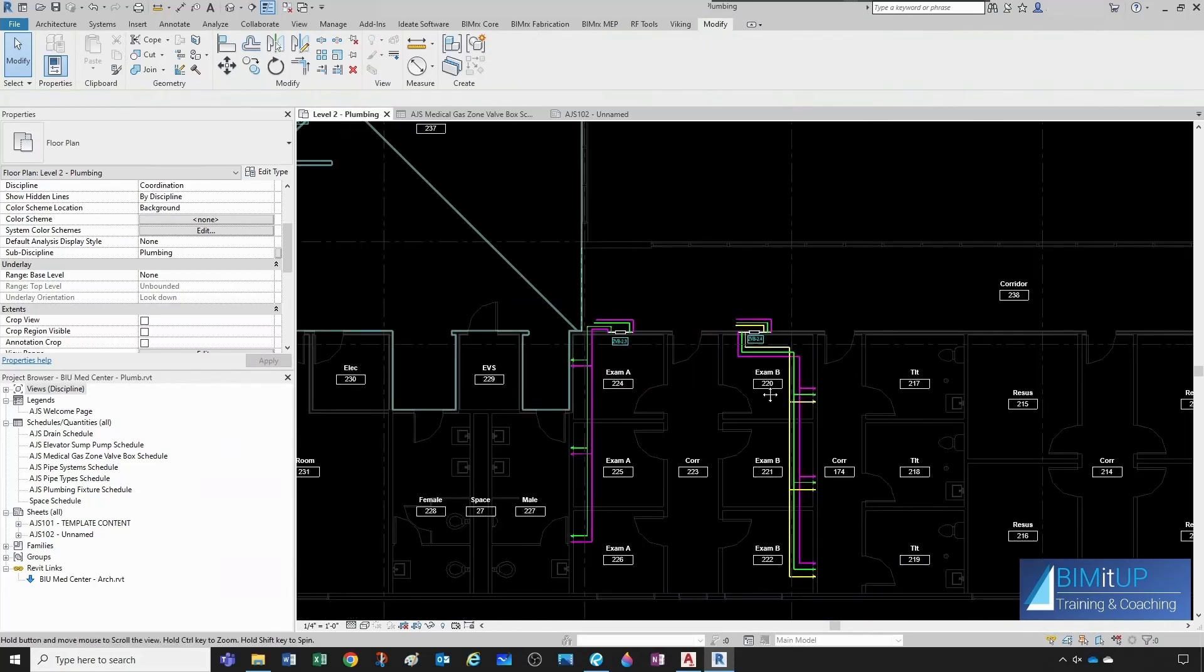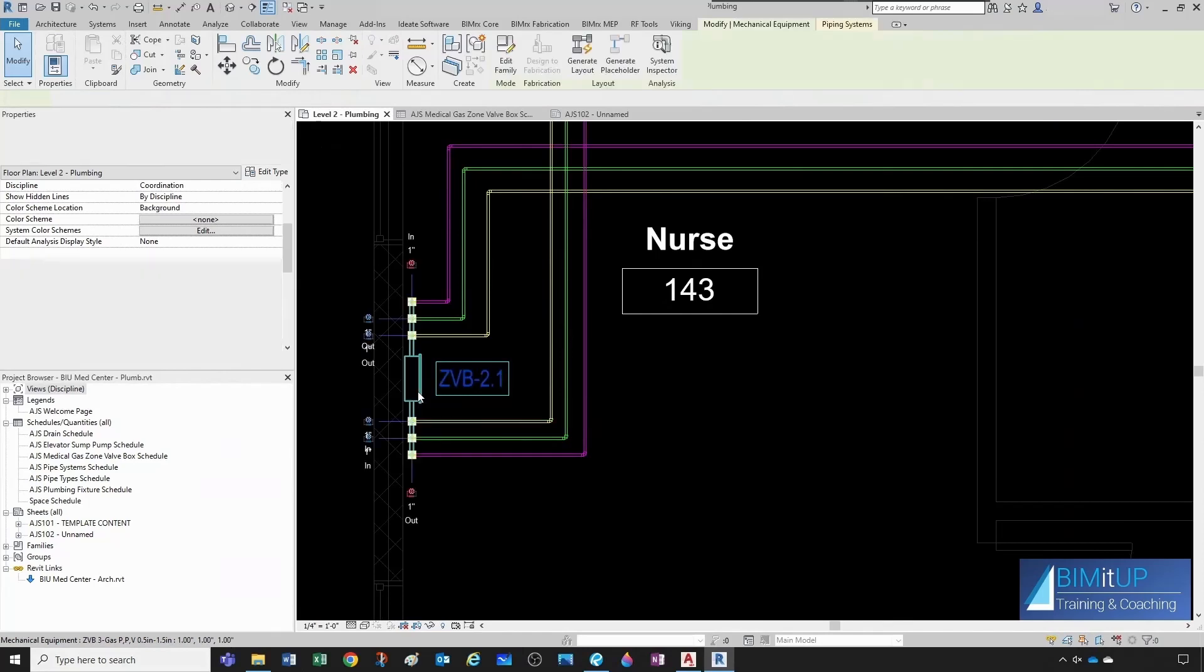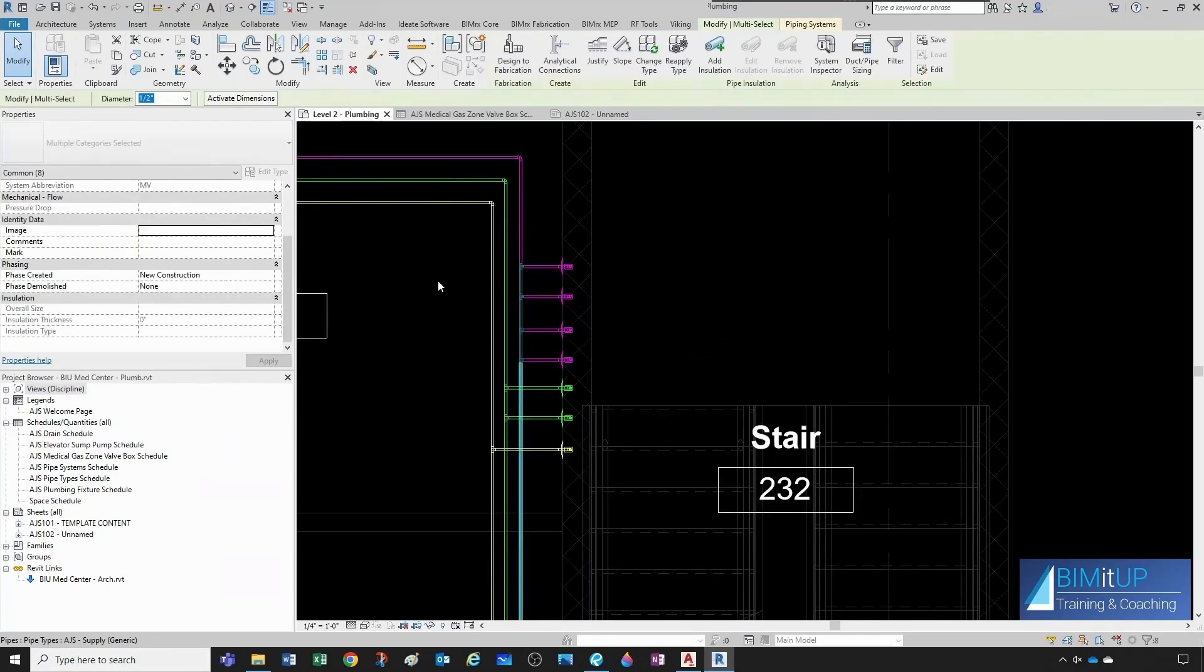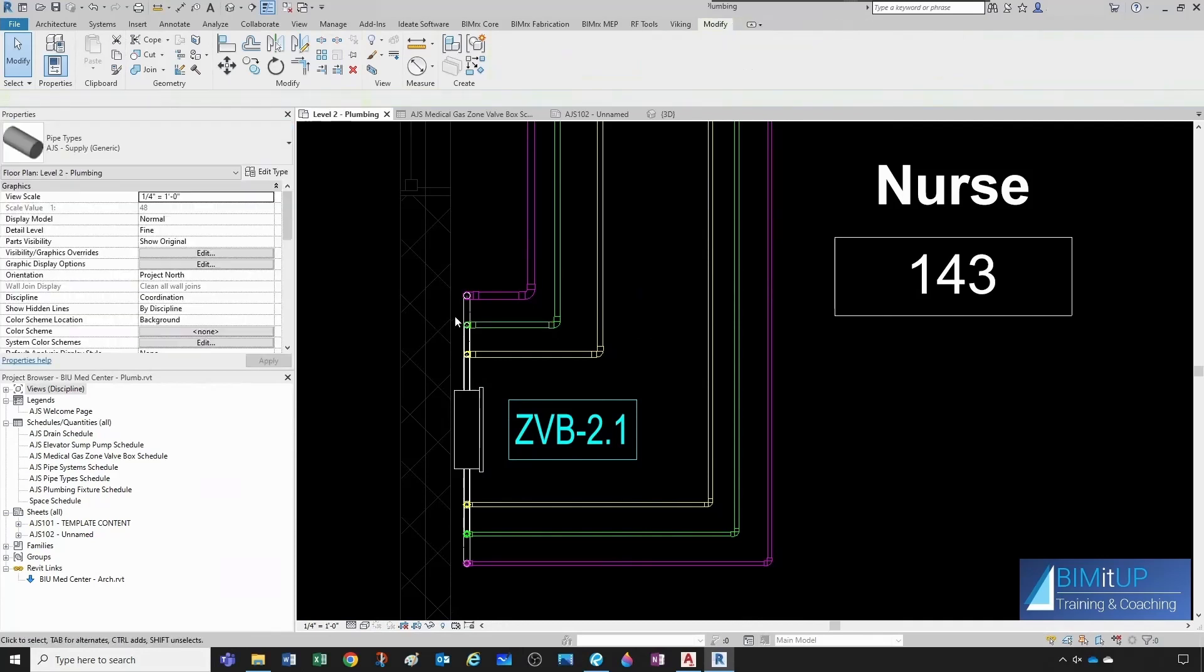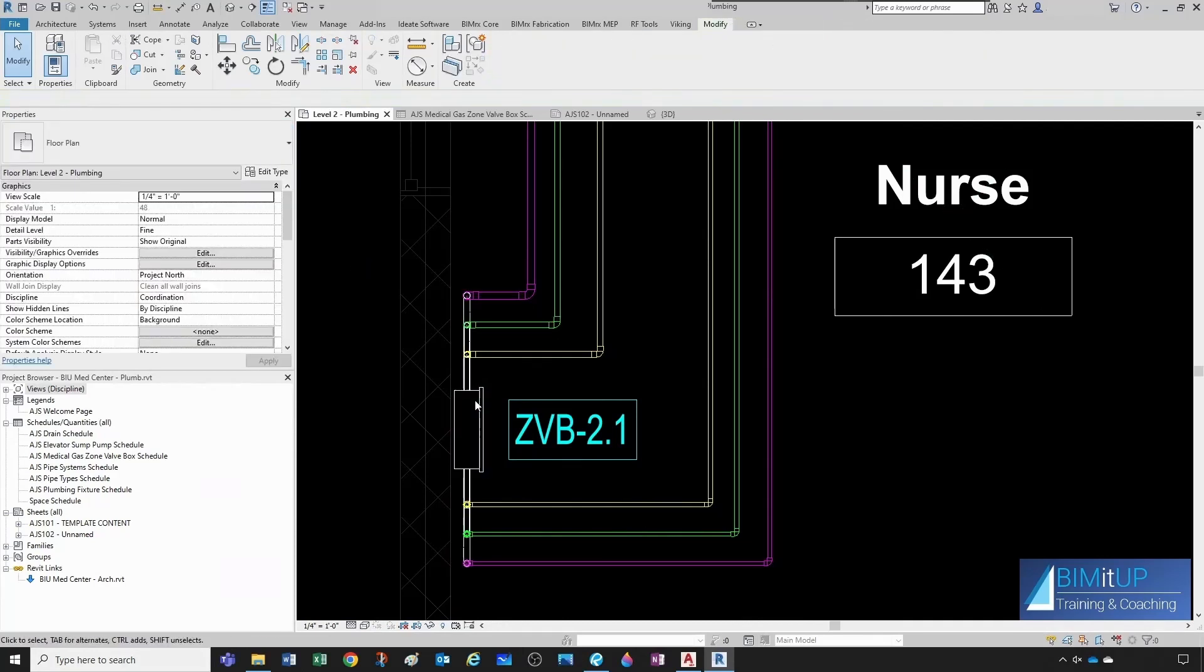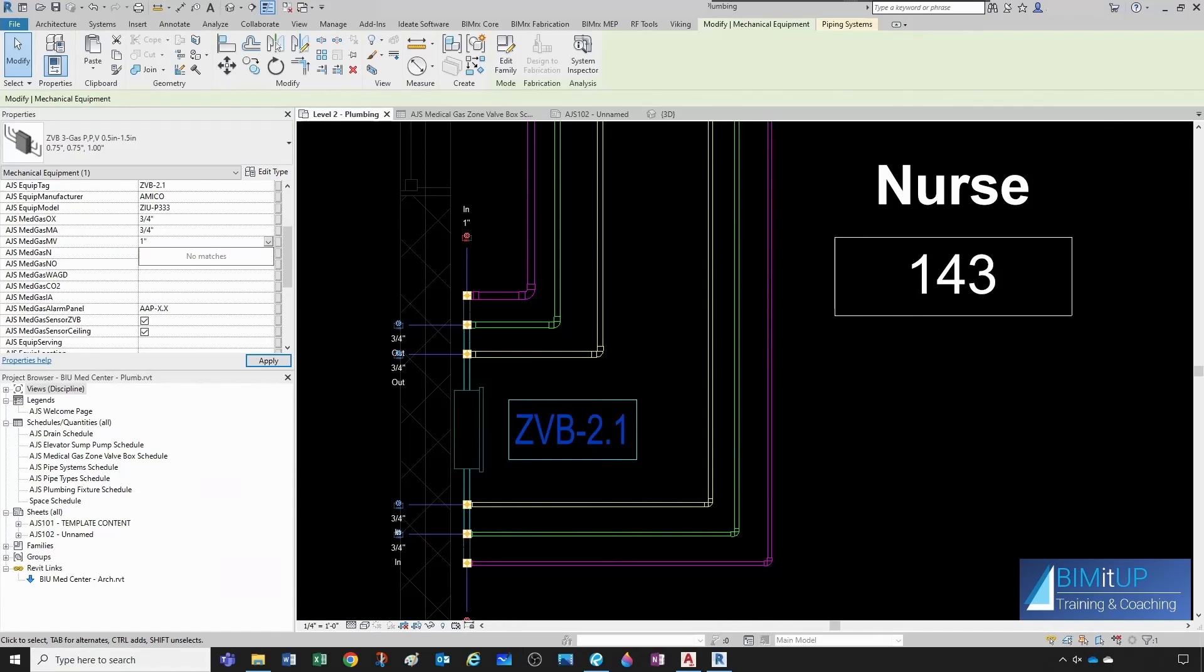There we go. Now we come to this other zone valve box. So this one here has three quarter inch medical air, three quarter inch oxygen, and one inch vacuum. So, three quarter inch medical air, three quarter inch oxygen, and one inch medical vacuum, and it has nothing else.